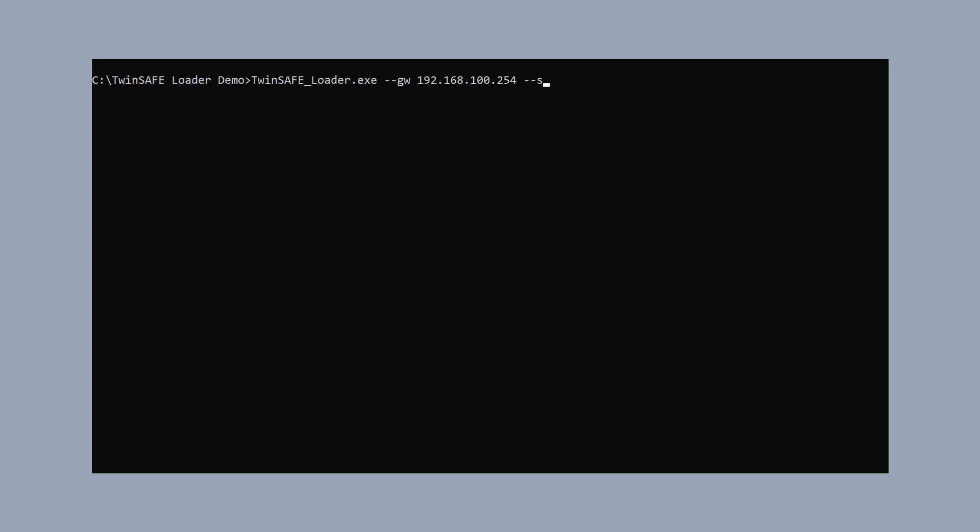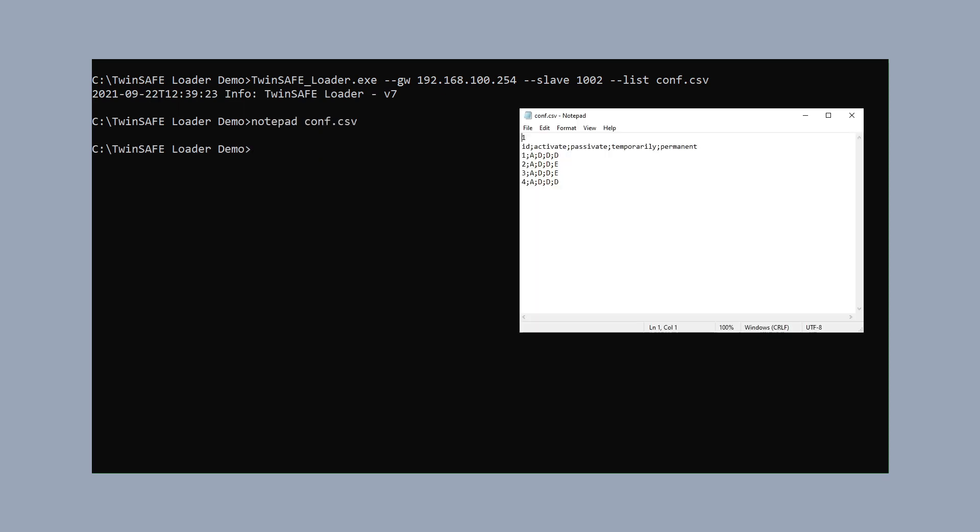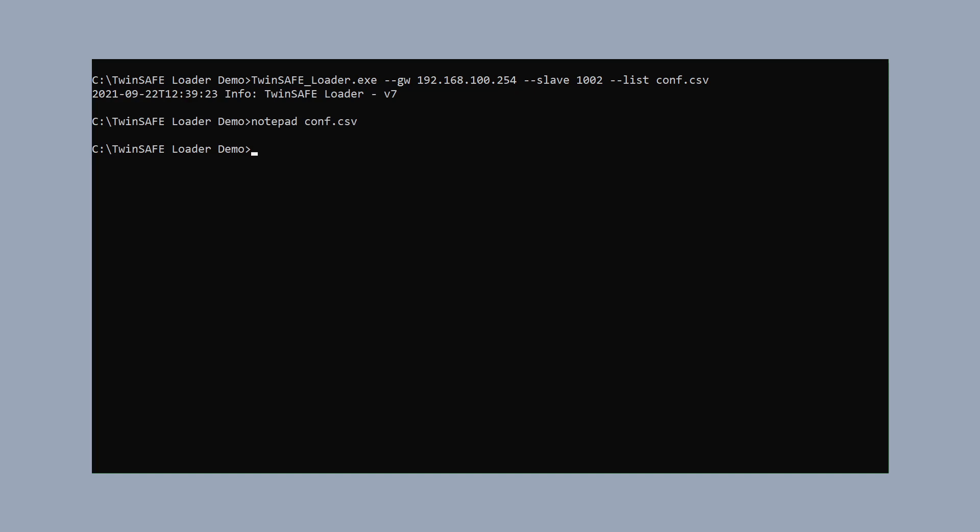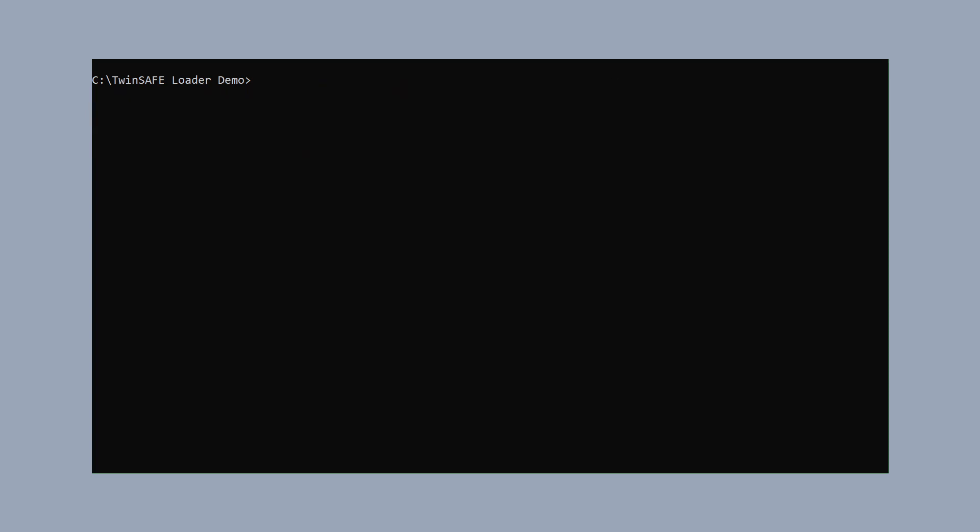And, in order to deactivate the group, we change the configuration, save the list, and with the same command line, only with another additional parameter with the additional parameter customize. And, as argument, our list we just configured, we can start the customization project, and after the command line has finished, the second TwinSafe group was successfully deactivated.